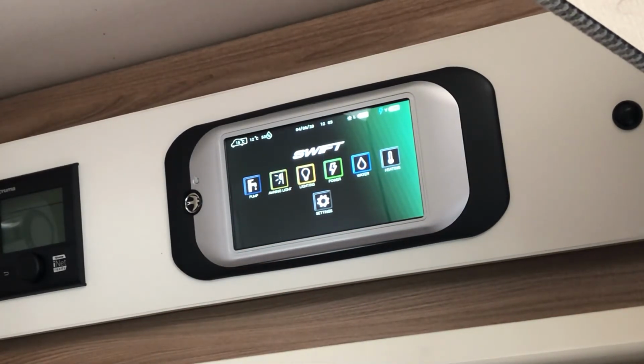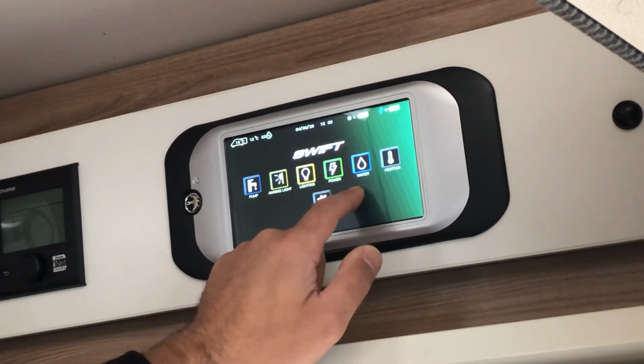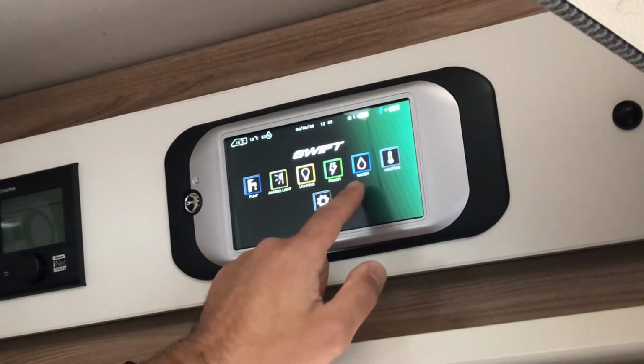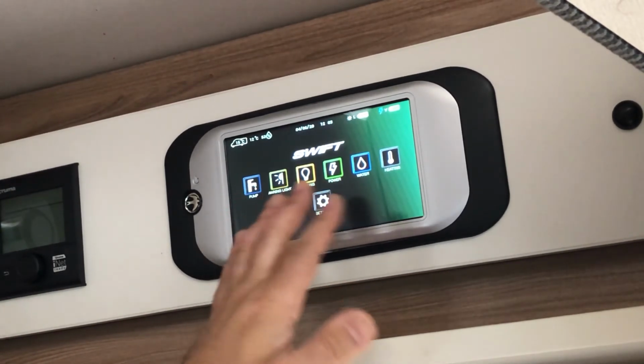Okay, in terms of fault finding, these panels are pretty bulletproof, but there's a couple of things that can happen, especially over the course of time and use. One of the things, being a touchscreen device, the calibration can throw itself out a little bit. So if, say, you're pushing this section of the screen, you actually find you're going into the settings. The panel's not broken, it's just the calibration's moved around.